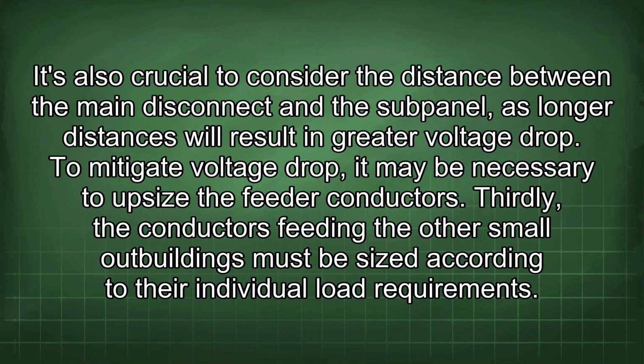It's also crucial to consider the distance between the main disconnect and the subpanel, as longer distances will result in greater voltage drop. To mitigate voltage drop, it may be necessary to upsize the feeder conductors.